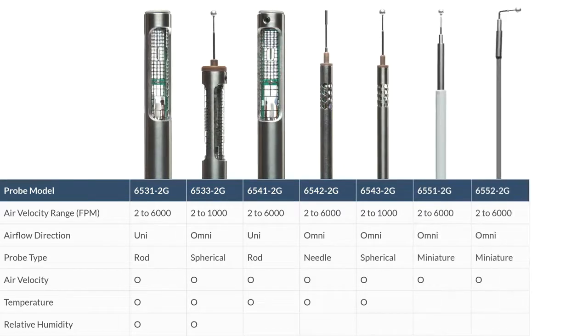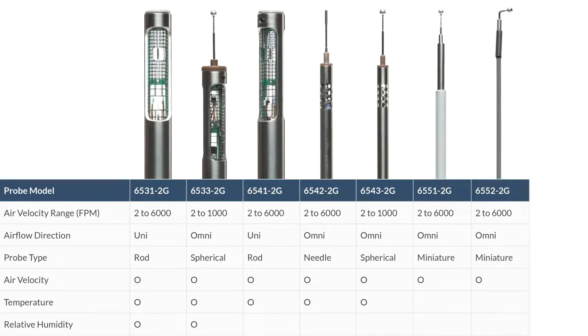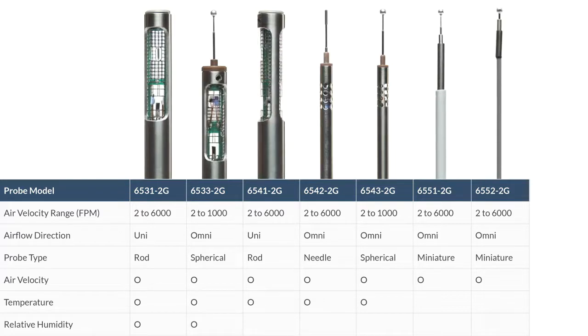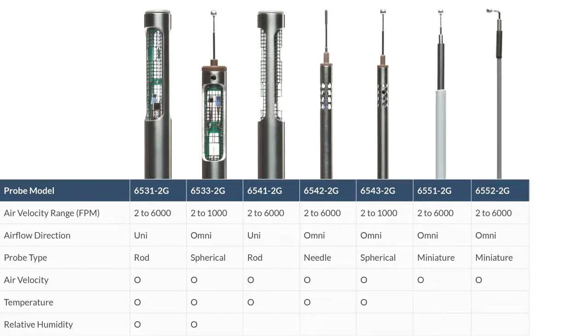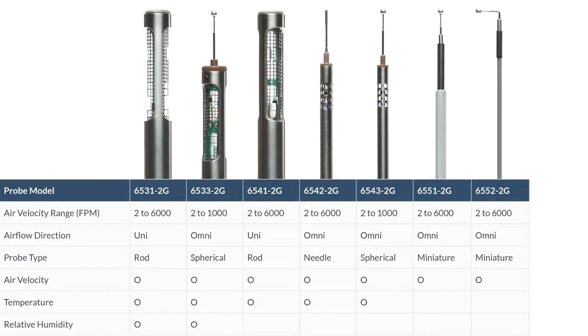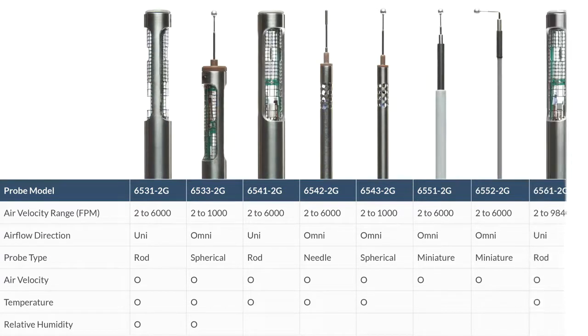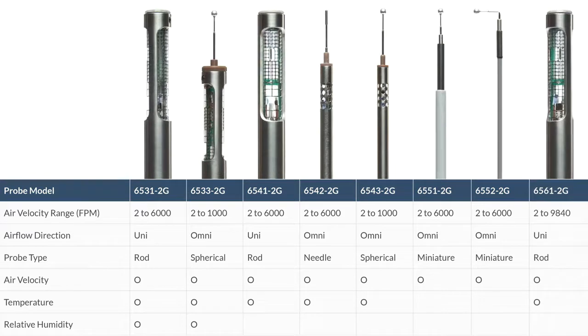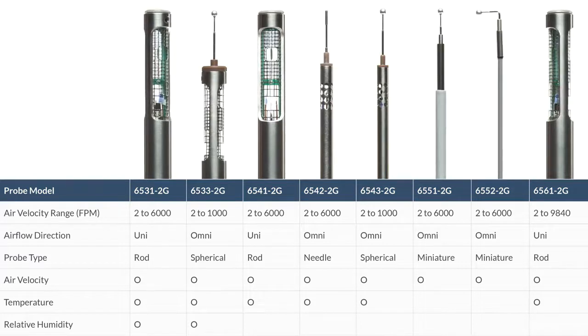Both probe models 6551-2G and 6552-2G are omnidirectional miniature-type probes capable of reading air velocity within a range of 2 to 6,000 feet per minute. However, the 6551-2G model has a straight form factor, and the 6552-2G model has a 90-degree bend for situations when your probe cable would otherwise get in the way of the probe sensor. And lastly, probe model 6561-2G is a unidirectional, rod-type probe capable of reading air velocity and temperature within an air velocity range of 2 to 9,840 feet per minute.